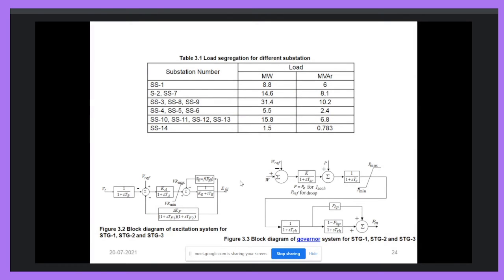and governor system. So what is the role of this excitation system? The excitation system is utilized to control the DC current, or you can say the excitation, to the generator. The excitation system will be responsible for managing the reactive power balance in the system. As the exciting current, or DC current, to the field winding changes, the reactive power output of the generator will change. We know that; we have studied this in machines. So the excitation system will be responsible for managing the reactive power balance of the system, and the governor system is responsible for managing the frequency of the system.